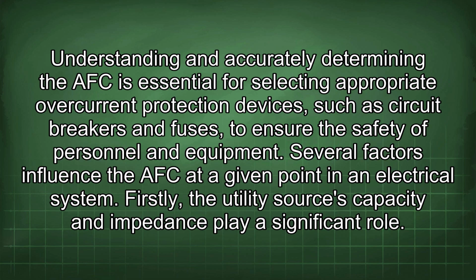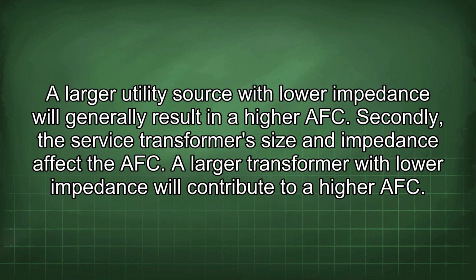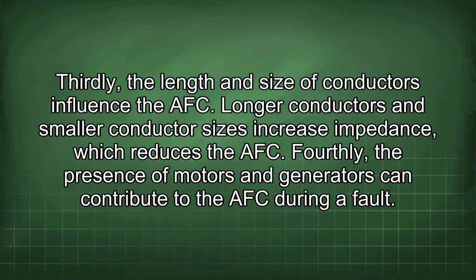Several factors influence the AFC at a given point in an electrical system. Firstly, the utility source's capacity and impedance play a significant role. A larger utility source with lower impedance will generally result in a higher AFC. Secondly, the service transformer size and impedance affect the AFC. A larger transformer with lower impedance will contribute to a higher AFC. Thirdly, the length and size of conductors influence the AFC. Longer conductors and smaller conductor sizes increase impedance, which reduces the AFC.